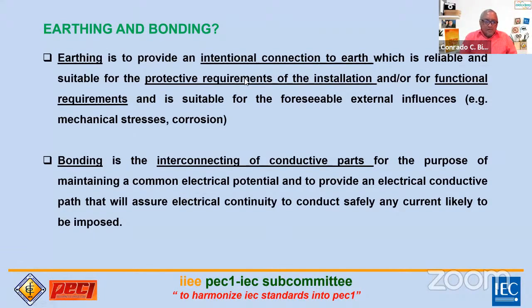It's still a protective measure, for safety of our equipment. That's what's important here. Then bonding is the interconnection of conductive parts or exposed conductive parts for the purpose of maintaining a common electrical potential and providing an electrically conductive path that assures electrical continuity to safely conduct any current likely to be imposed. It goes back to the source, and when you have bonding, your OCPD will react accordingly based on its settings, on whatever fault it senses, like a ground fault.